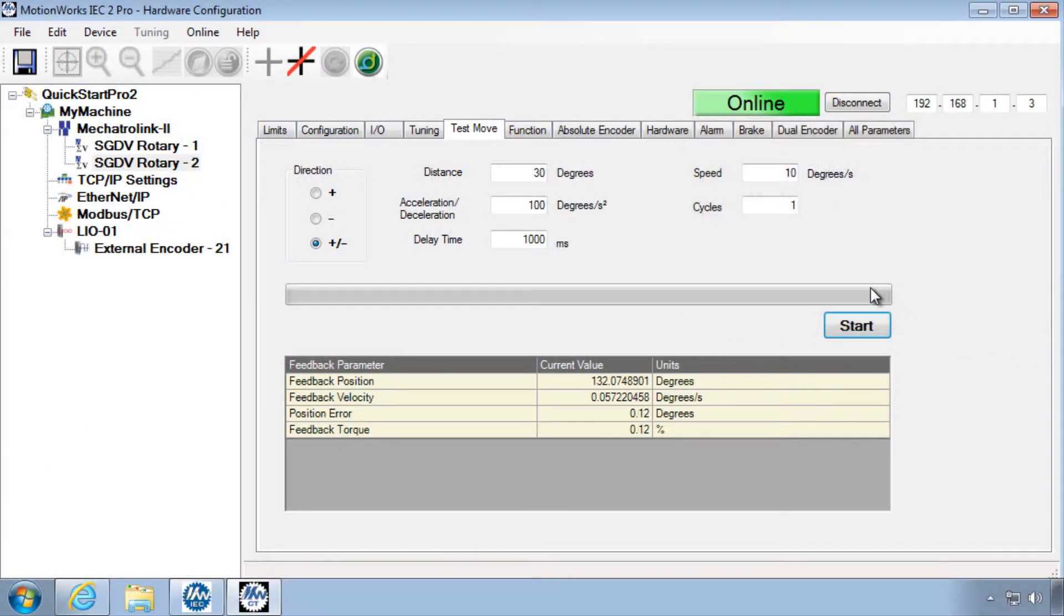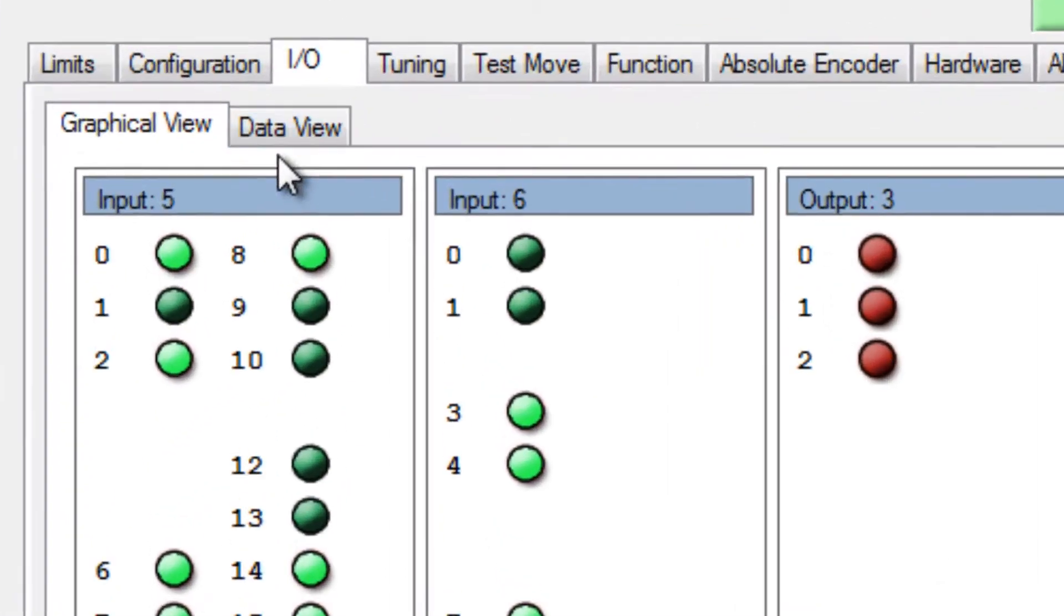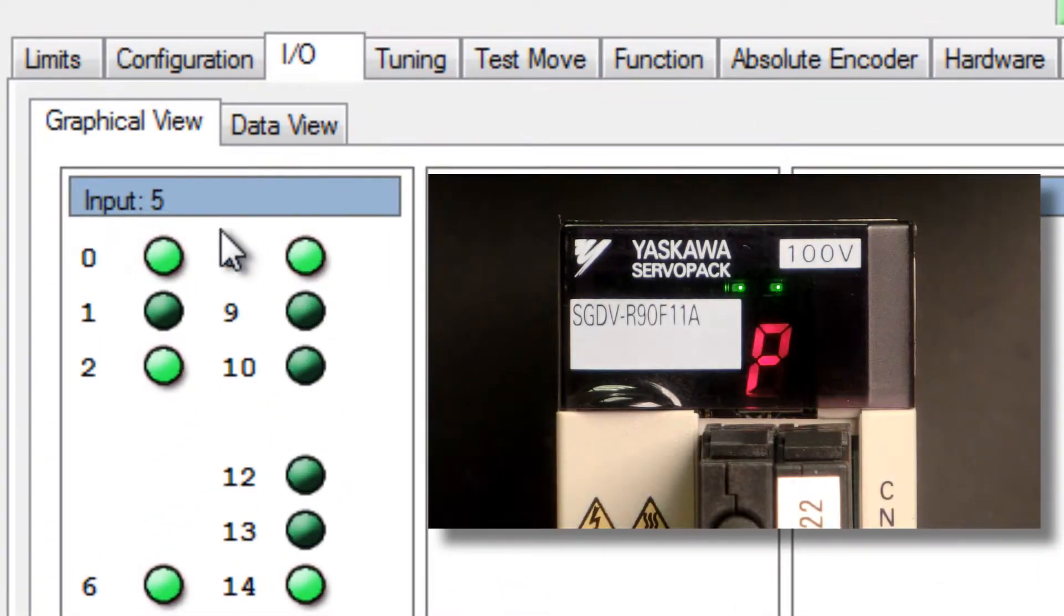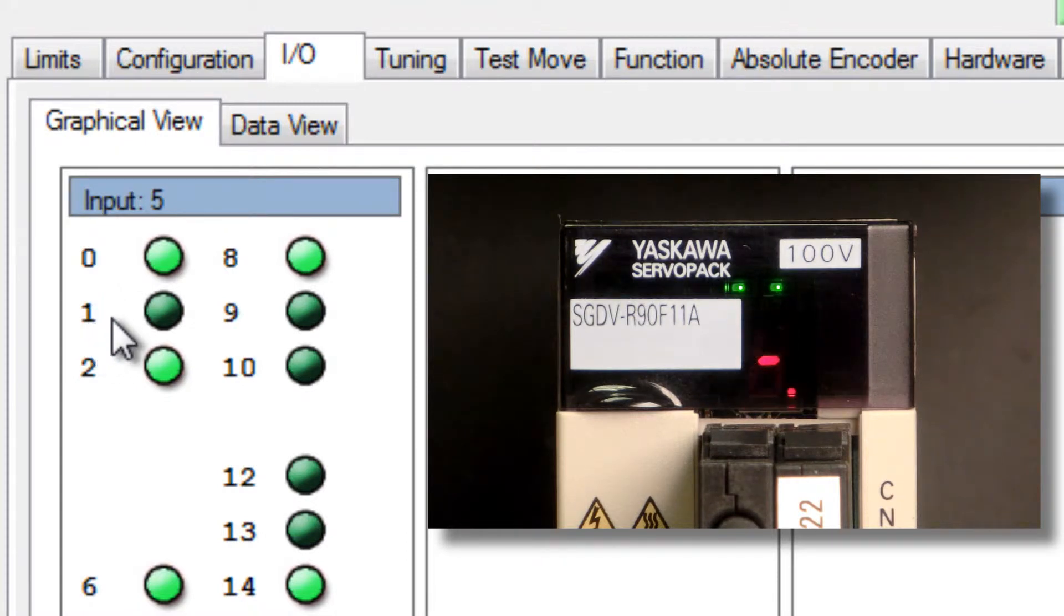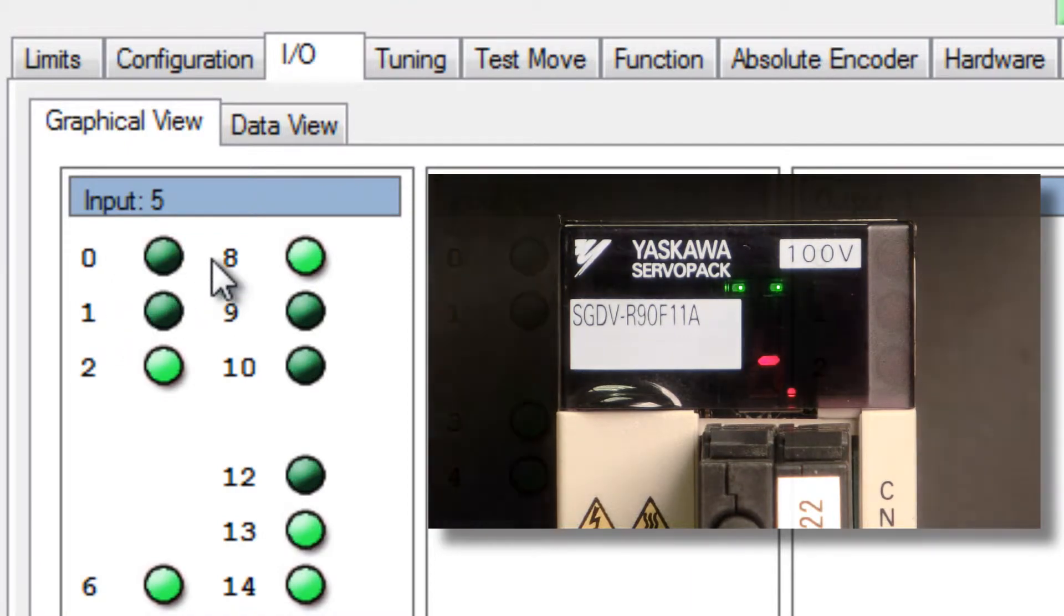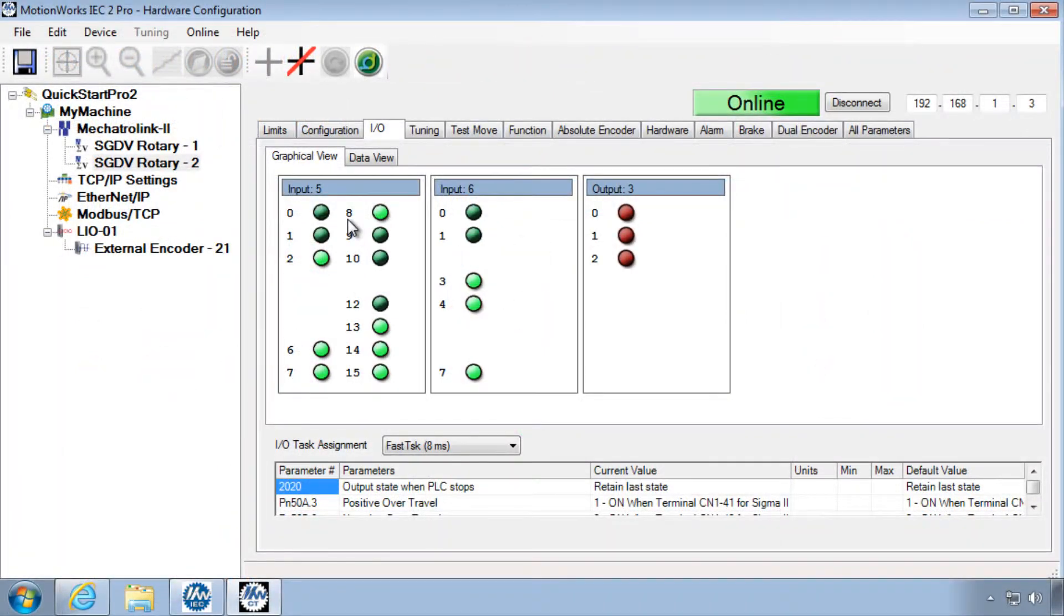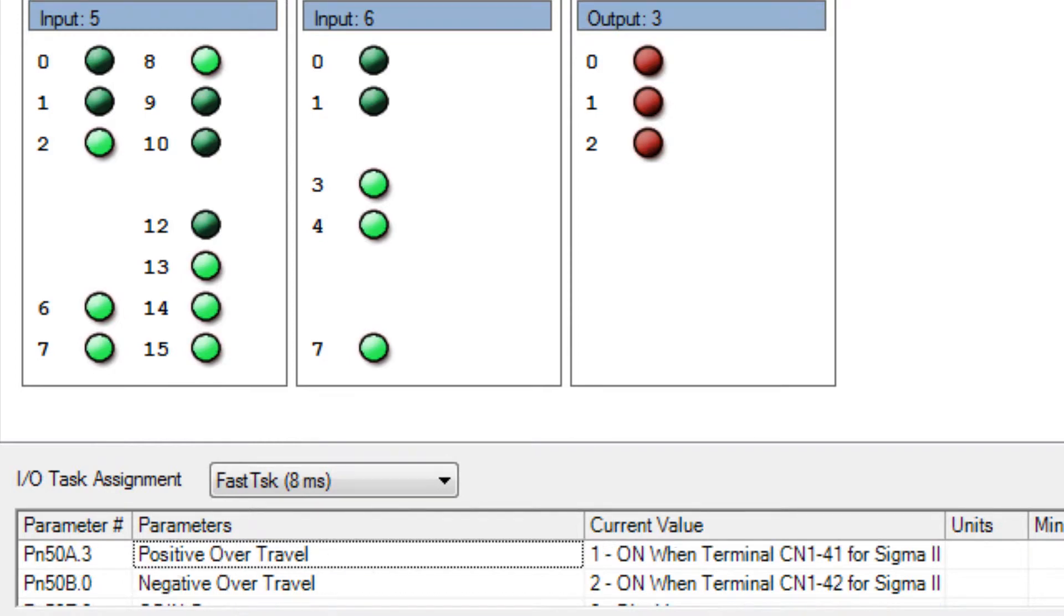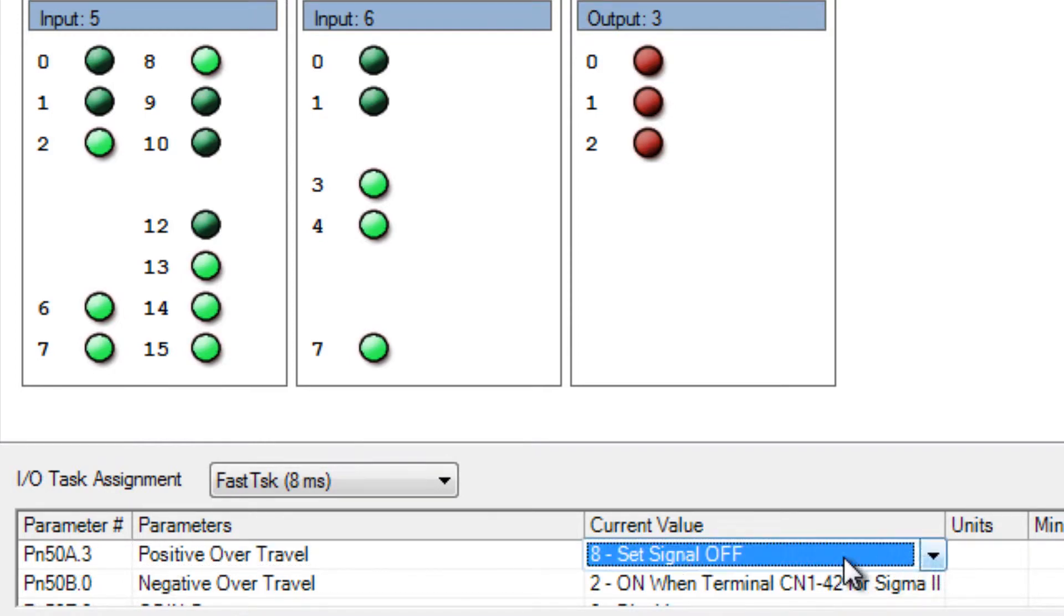Over-travel input status can be monitored in the I/O tab under input 5 indicators 0 and 1. You can see here I just have a switch connected to the over-travel. If I turn that switch back on, it connects the over-travel sensor. If you want to disable the over-travel feature, you can do so under the I/O tab, positive over-travel and negative over-travel, by setting the current value to 8, set signal off.